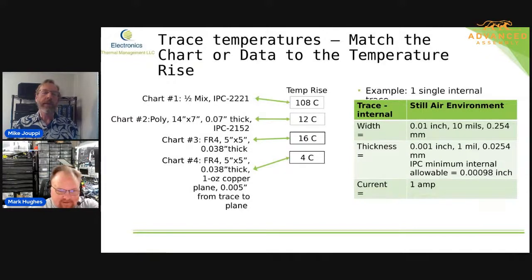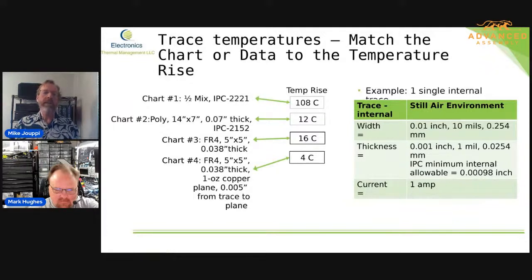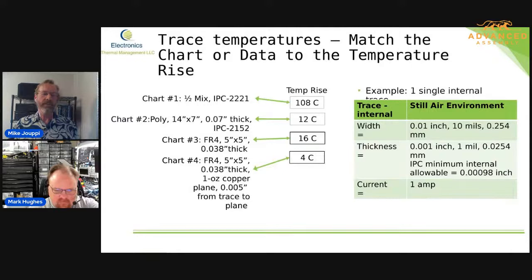The thing that is difficult there is that if you don't know the history behind these design charts, you wouldn't know that the design chart for internal traces in IPC-2221 is just half the current from the external trace chart — it's not from data that was collected. That had the whole community really confused for a long time until it surfaced through the research we did, finding the original data and also comparing it with the equations being used to define the 2221 charts. You'll see a factor of 0.5 on them and the same equation, so it's pretty obvious once you take a look at them.